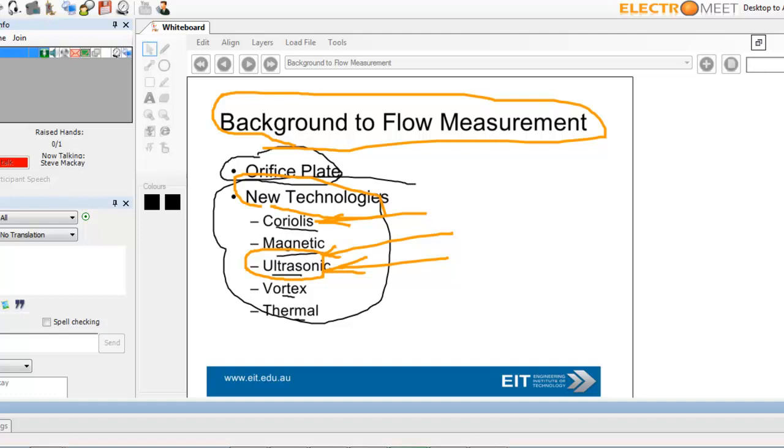The other two are Vortex. Vortex is based around the principle of the Von Karman principle, or Von Karman effect, where your flow generates vortices when going past a bluff body, like a block. And the flow velocity is proportional to the frequency of the vortices. So a bluff body is just a piece of material with a broad, flat front at right angle to the flow.